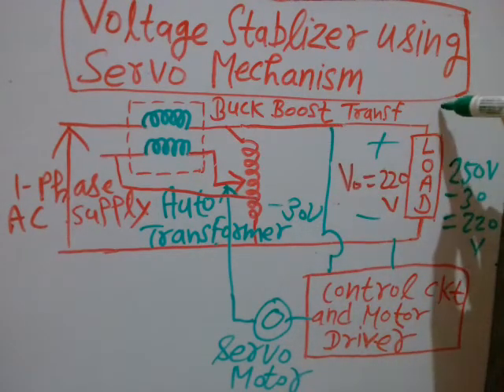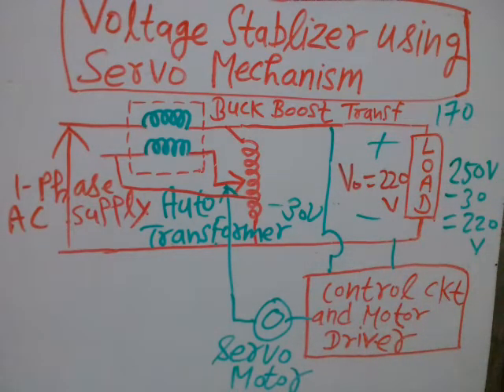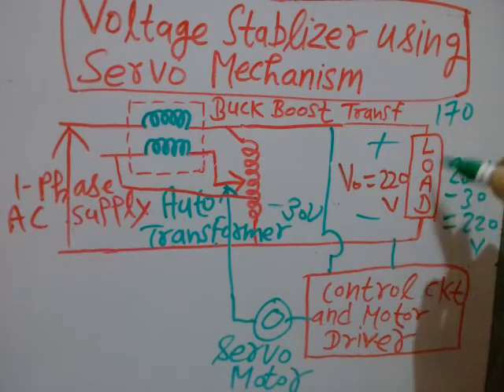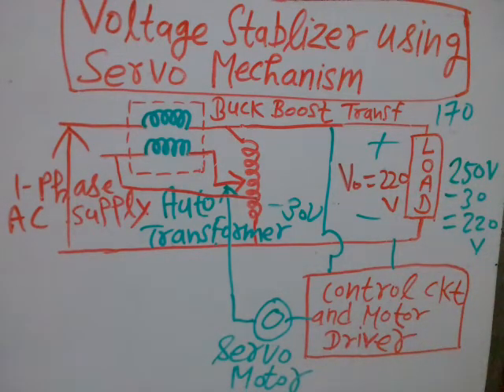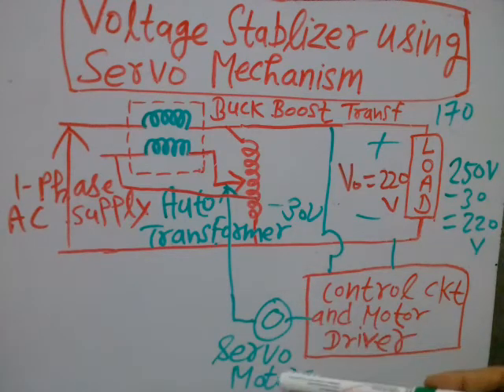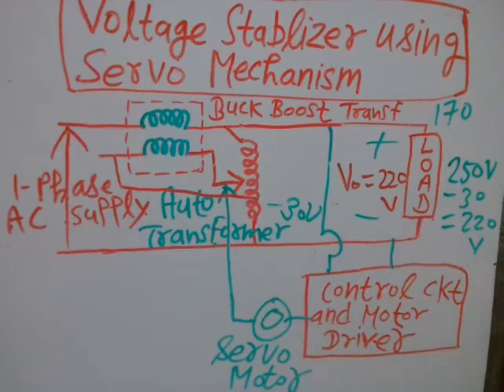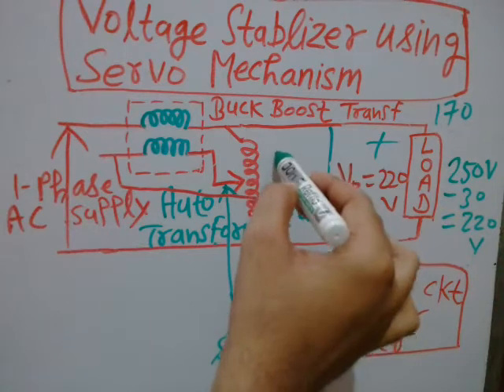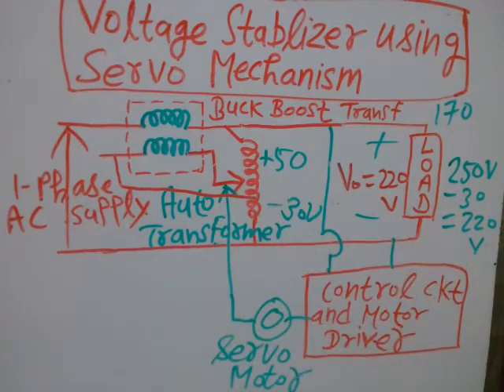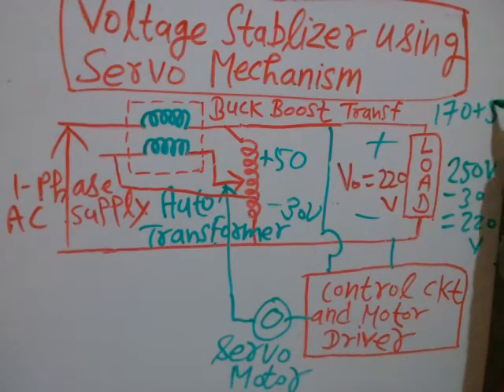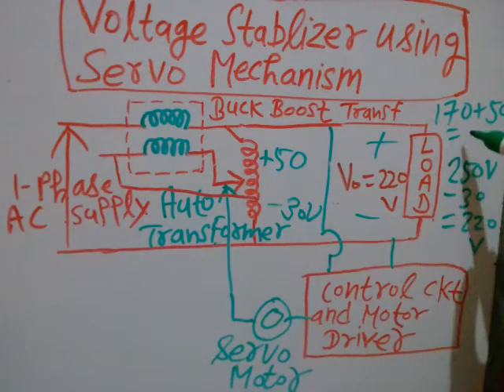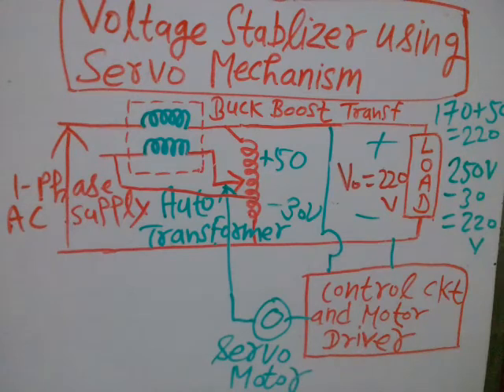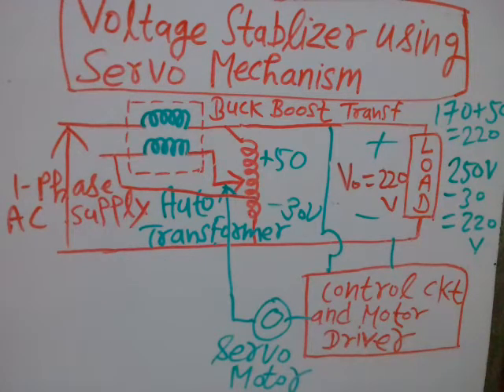Similarly, if an under-voltage of 170 volts appears across the load — which is 50 volts below the rated 220V — the control circuit senses this abnormality and sends a command signal to the servo motor. The servo motor moves the stylus to produce a compensating voltage of plus 50 volts, which is added so that 170 plus 50 equals 220 volts at the load.